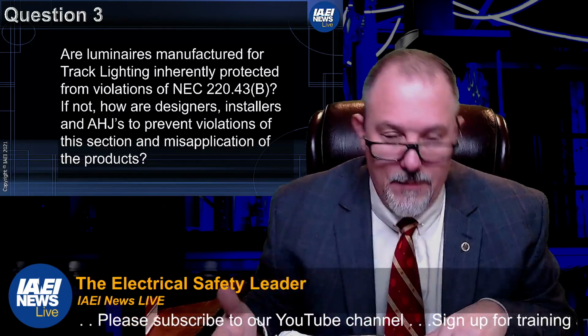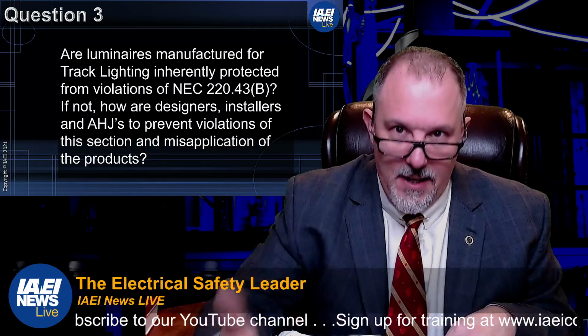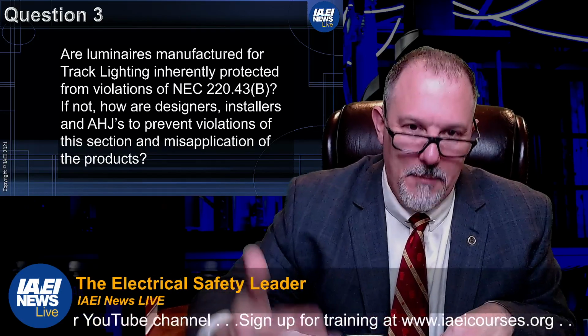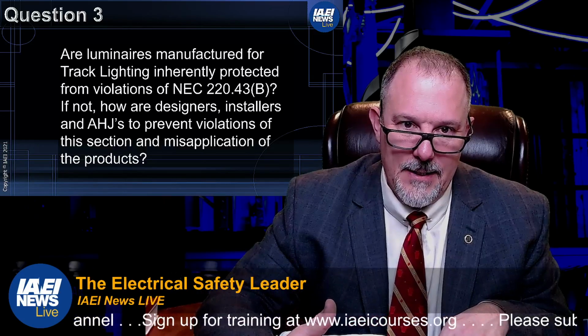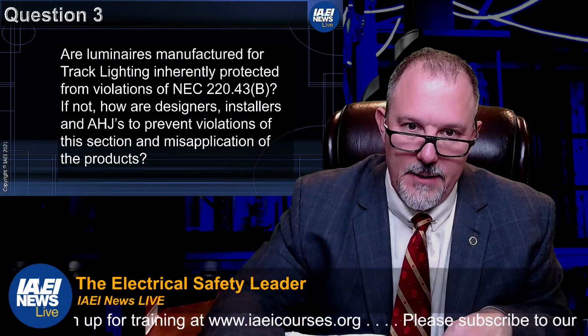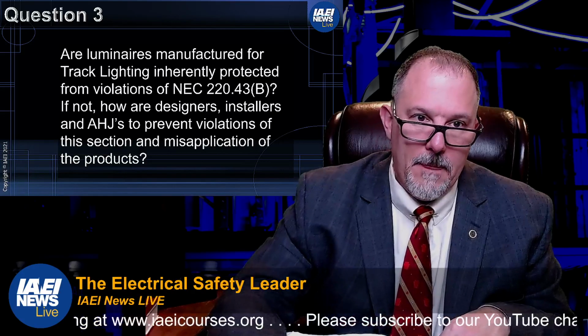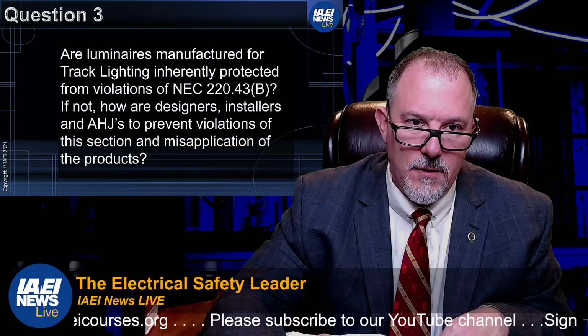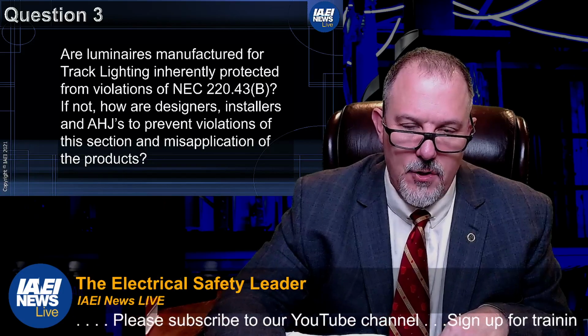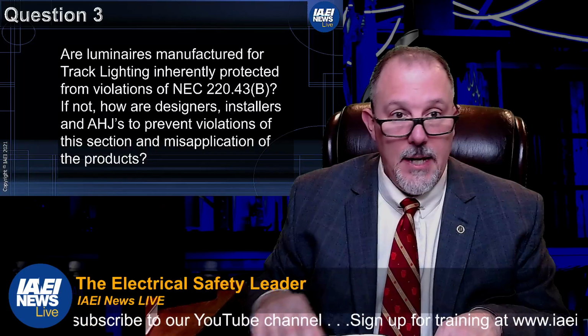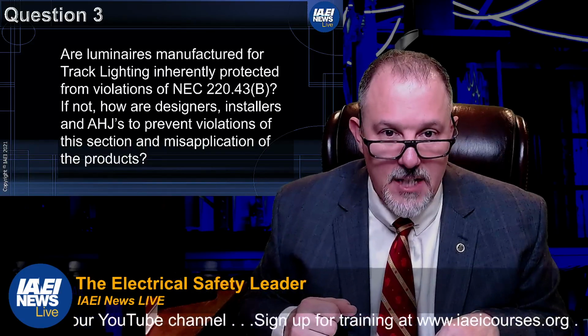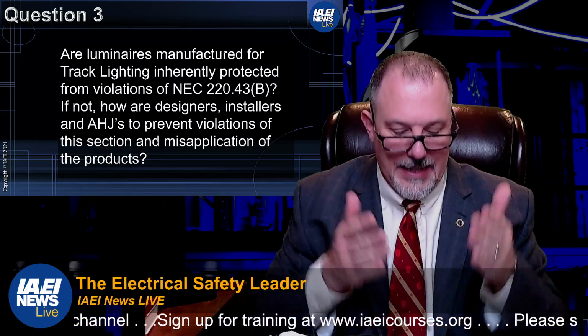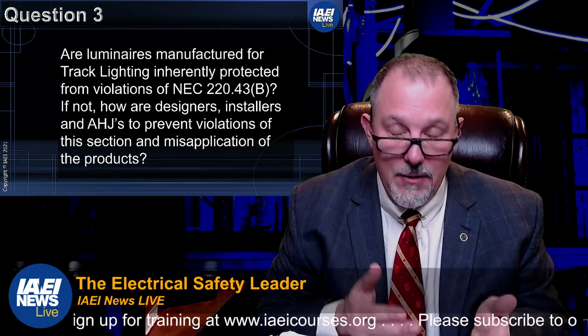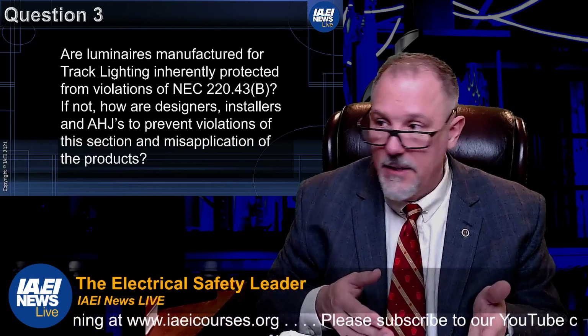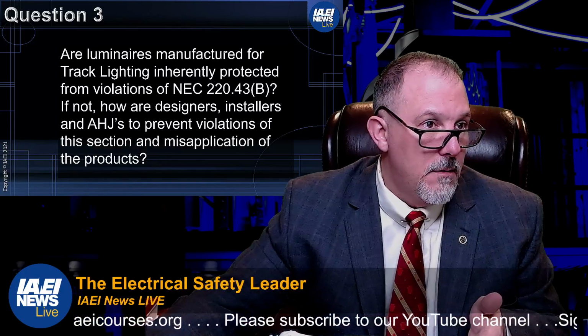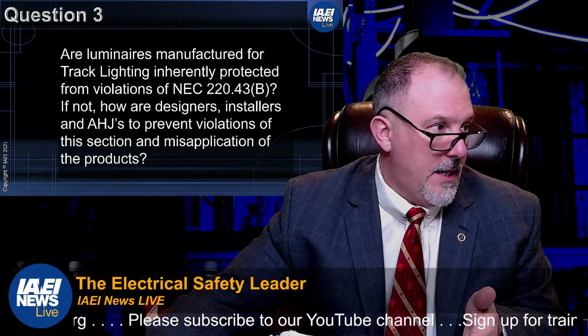If a manufacturer who makes track lighting is not thinking about 220.43(B), guarantee it. So are luminaires manufactured for track lighting inherently protected from violations of 220.43(B)? I would say no. If not, how are designers, installers, and AHJs to prevent violations of this section? This section is a calculation. So to prevent violation, you have to do your calculation correctly. You have to understand the installation, right?